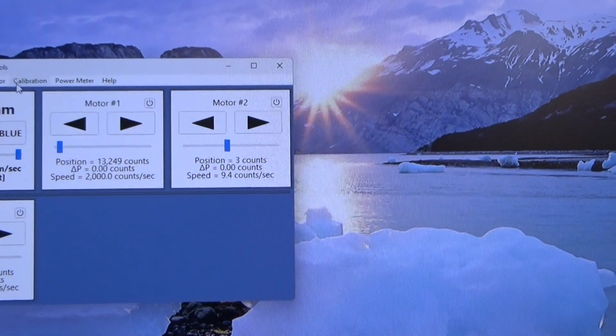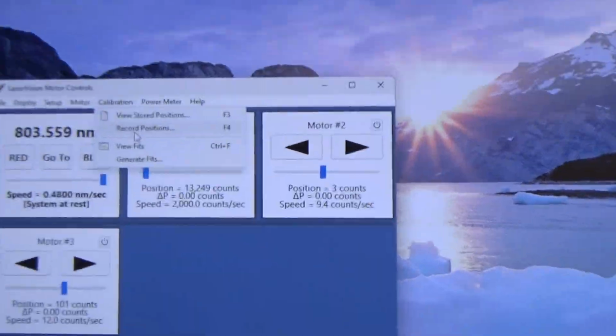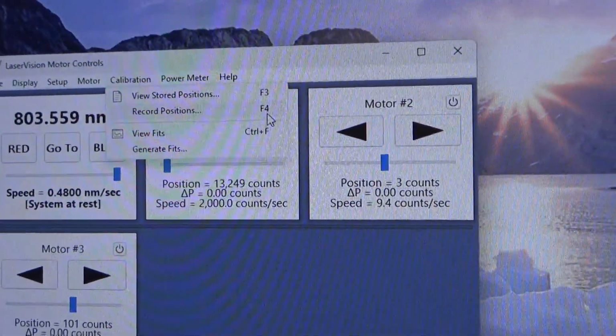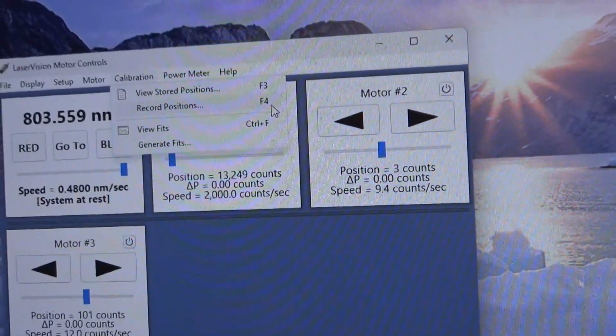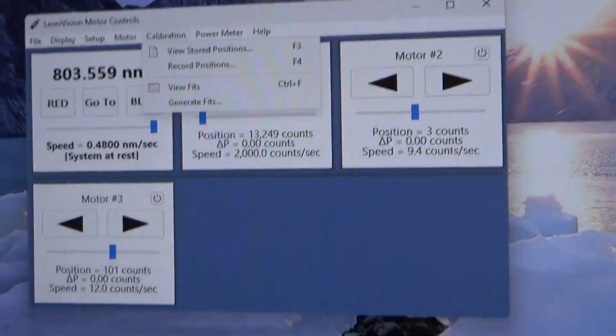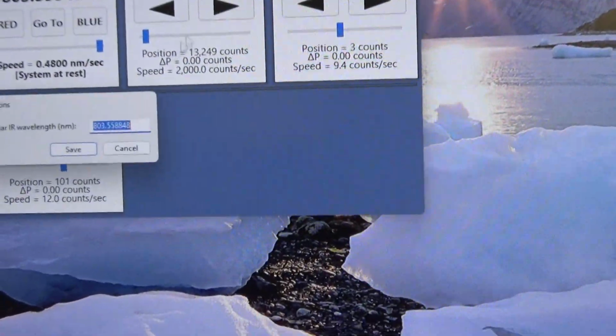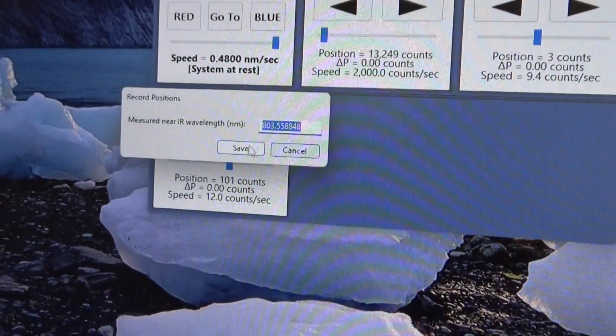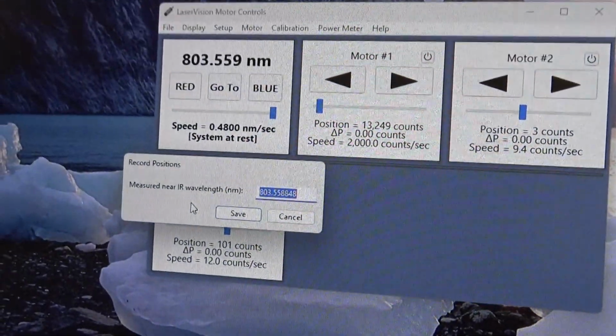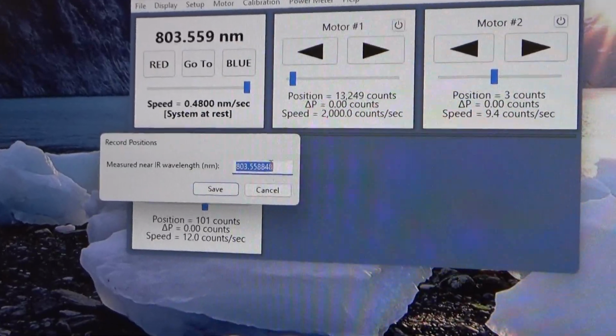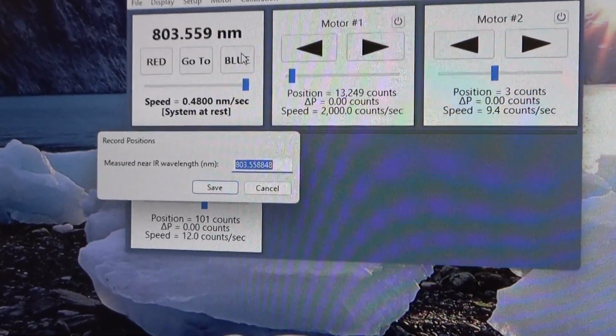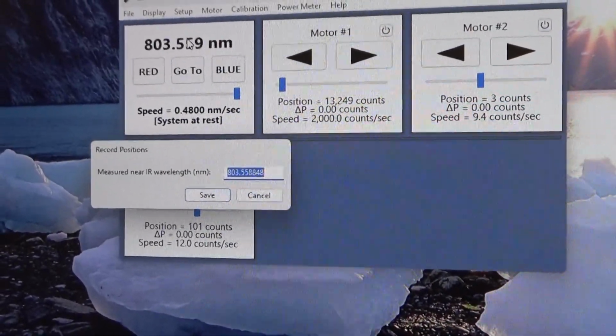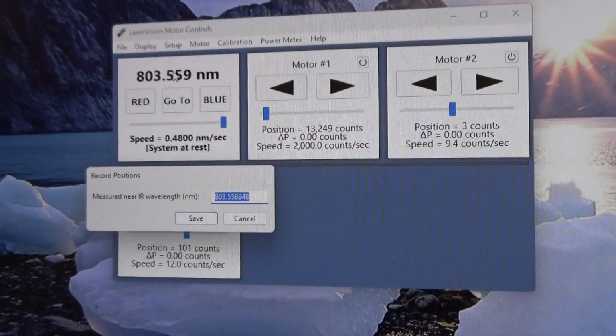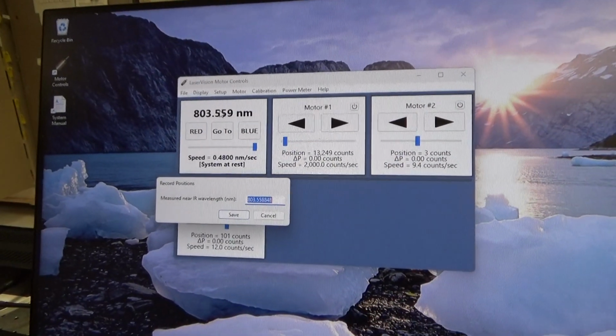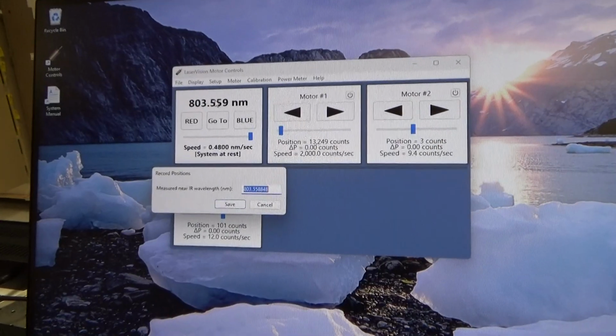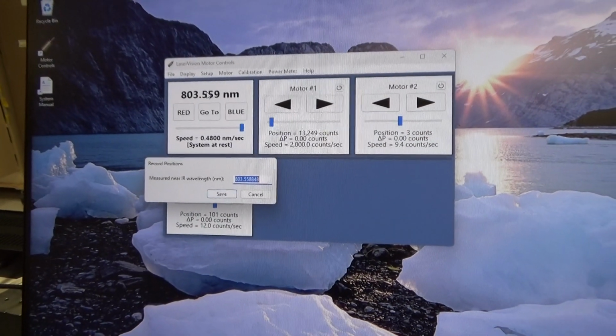If you go into calibration, you can see there's this record positions. The equivalent would be to press the F4 key, and a window will pop up and it will ask you what the measured wavelength is. It comes pre-populated with the actual wavelength that's displayed. So if you're using a wave meter to determine the wavelength of the output from the oscillator, you can enter that value in.